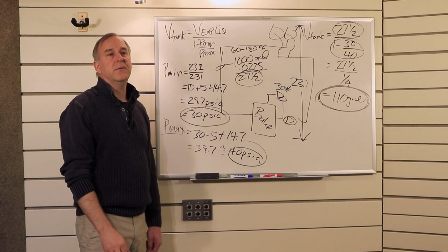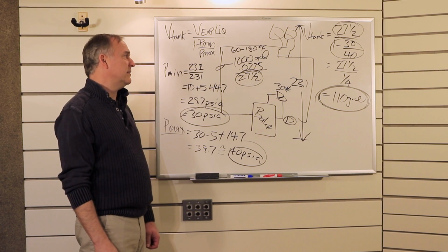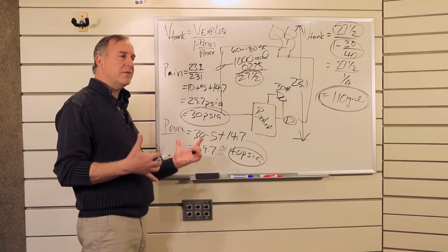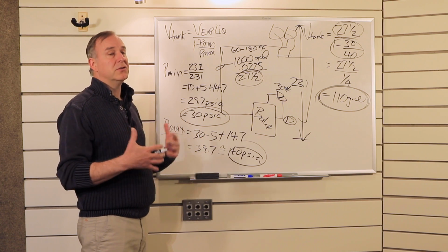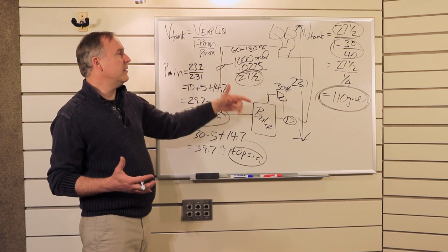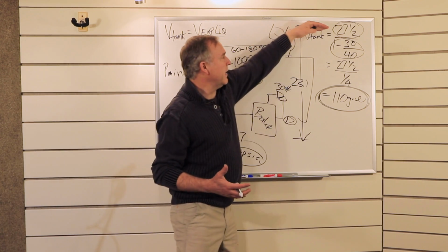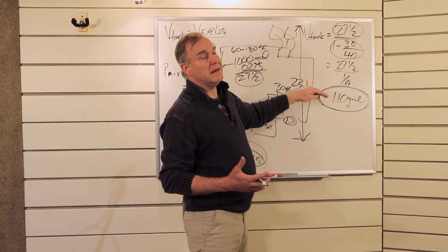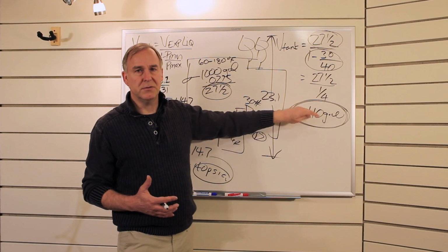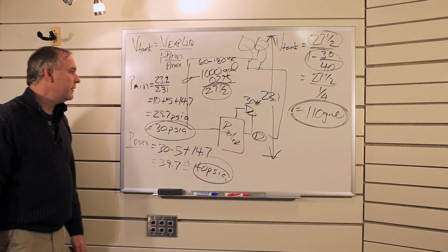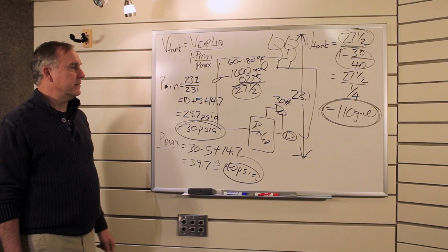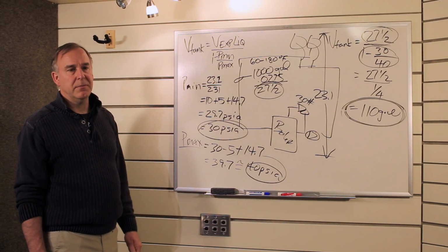are both significant when you're selecting a tank. One is the acceptance volume that's required. In other words, how much expanded water I have to deal with. I have to make sure that I have a bladder. You know, for example, if I had a partial acceptance tank, I have to make sure I have a bladder that would accommodate 27.5 gallons. So I need to meet both those criteria. I need to make sure my bladder can accommodate this expanded volume of water, but I need to make sure my total tank volume of 110 gallons is going to be adequate as well in terms of the air charge I need. So that is the basic idea on how you go ahead and calculate by hand a bladder style expansion tank.